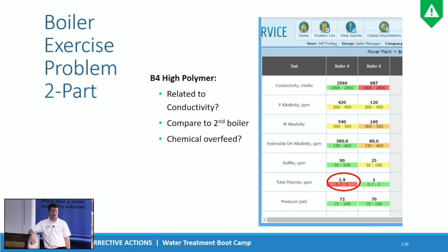The set points are not wrong. So if conductivity is in range, it should be in range, right? Mm-hmm. But it's not in range. So do we think that's because we're overfeeding, underfeeding, feeding the right amount? I think we might have to look at the duration of the pump. Okay.